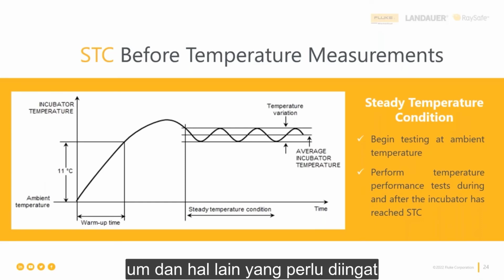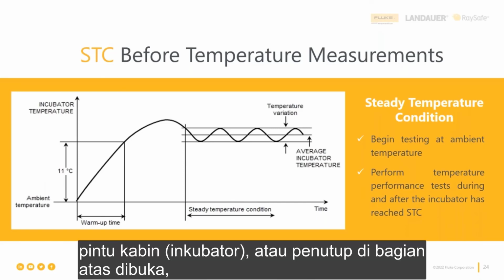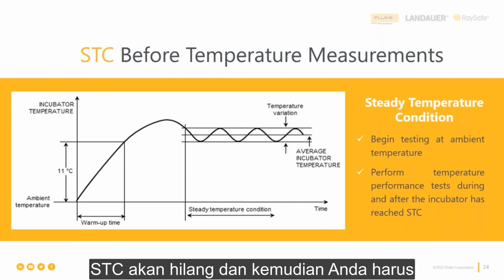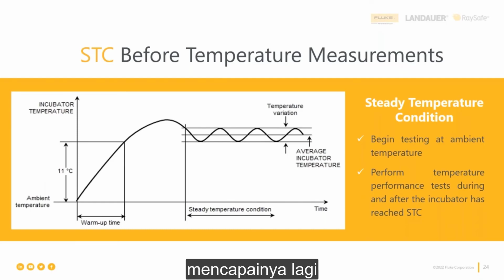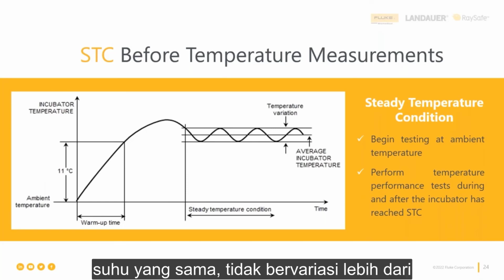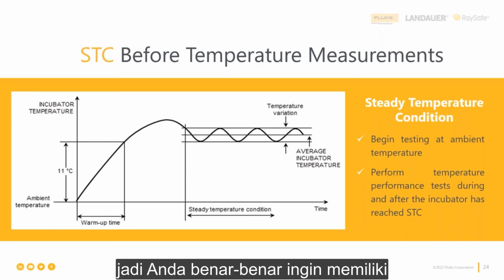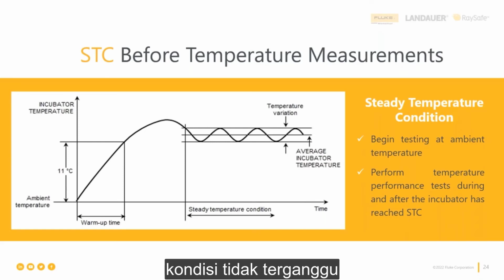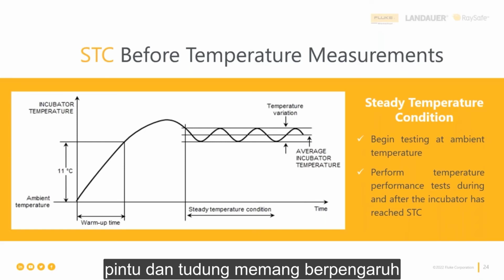And the other thing to keep in mind is every time a porthole on the side or the cabin door or hood at the top is opened, STC is lost, right? And then you have to achieve it again. So STC being the same temperature, not varying within 1 degree Celsius over a period of an hour. So you really want to have that condition undisturbed. So just keep note that opening those doors and hoods does have an effect on that.